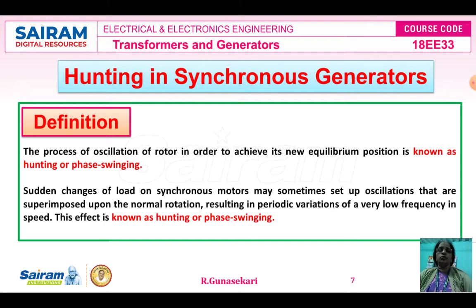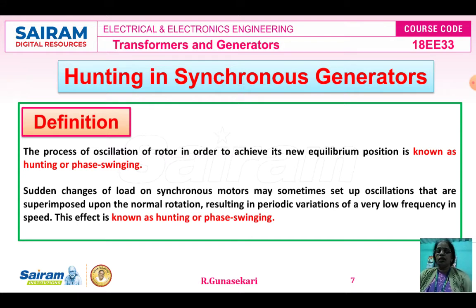When the rotor goes to its new equilibrium position under the sudden changes of load in the synchronous generator, every synchronous machine has a natural time period of free oscillation. If the driving torque of the alternator is pulsating, the rotor is pulled periodically ahead or behind its normal position. If this oscillation equals the natural time period of free oscillation, the condition is called hunting, also known as surging or phase swinging.